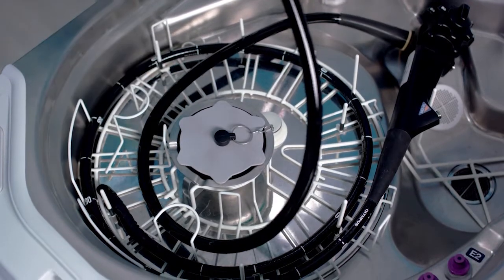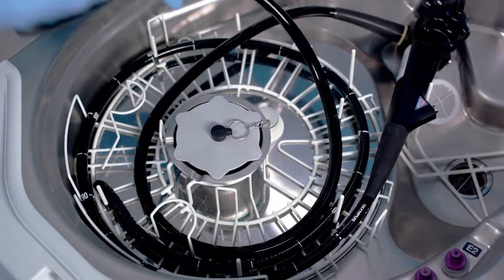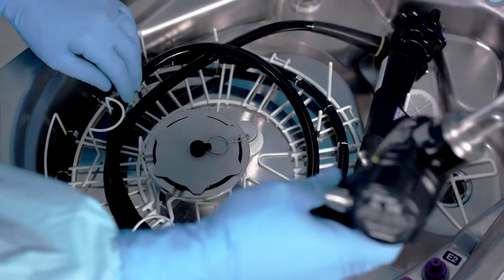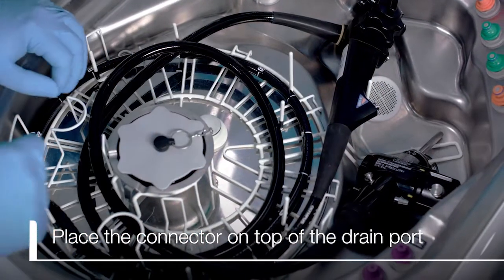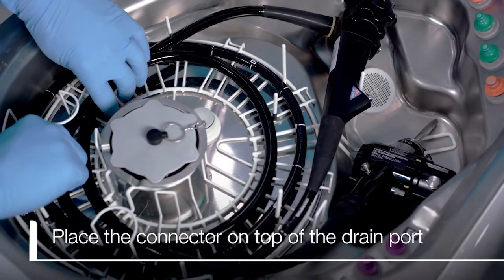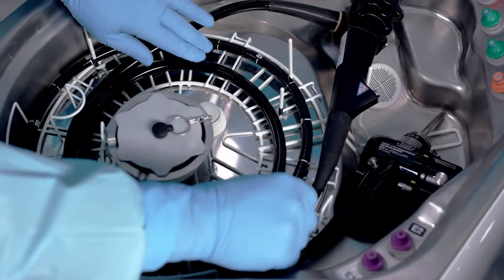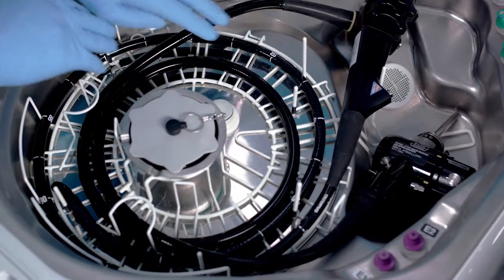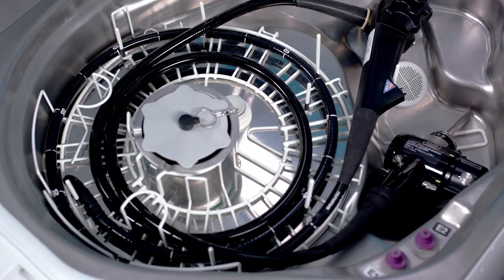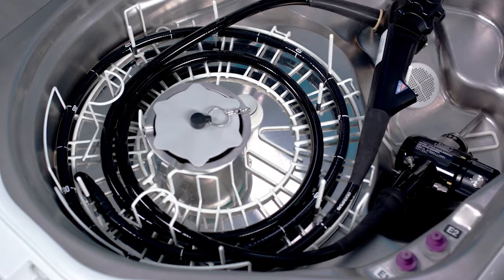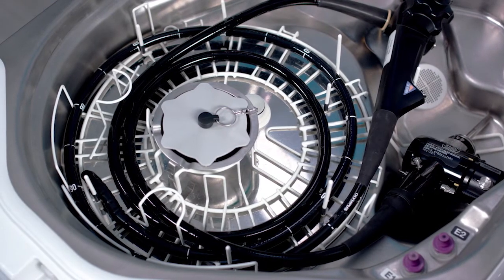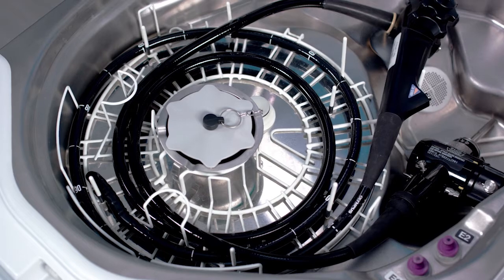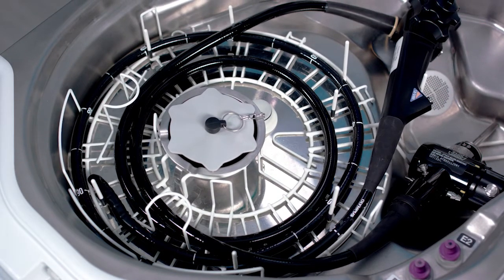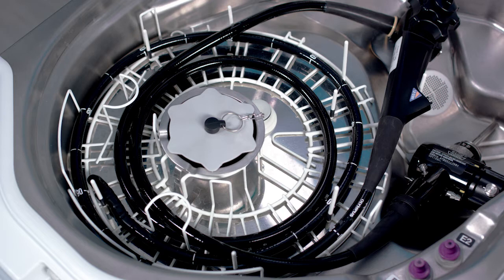With both the insertion tube and the universal cord loaded into the basin, it's time to place the endoscope connector inside of the OER-Elite. The scope connector gets placed directly on top of the drain port. This is a way to ensure the endoscope is loaded properly. Finally, make the necessary adjustments to minimize overlapping of the insertion tube and universal cord. Don't forget, certain Olympus endoscope models, for example, the ultrasonic probe and ultrasonic endoscope, may need to be loaded in a slightly different manner. The OER-Elite Quick Reference Guide will provide additional instructions.